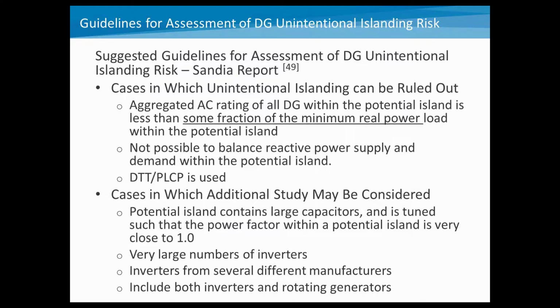Of course, we can talk about this in more detail in the question session, but in general, it said unintentional islanding can be ruled out in these types of scenarios. One, where the aggregated AC rating of all the DG is less than some fraction of the minimum real power within the potential island, and it is not possible to balance the reactive power supply and demand within the island. So again, this is looking at the probability and possibilities of having matched power, both real and reactive, inside the island. And the other condition is if direct transfer trip or permissive power line carrier is used, you can pretty much rule out that unintentional islanding would occur.